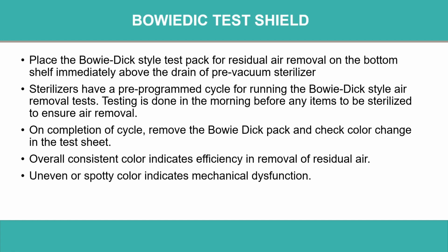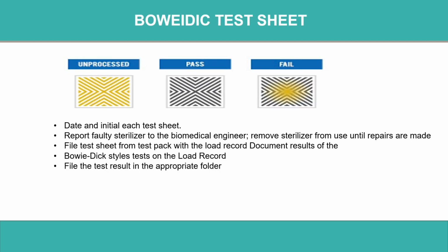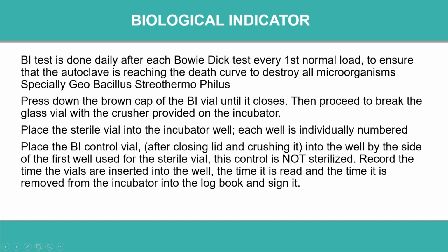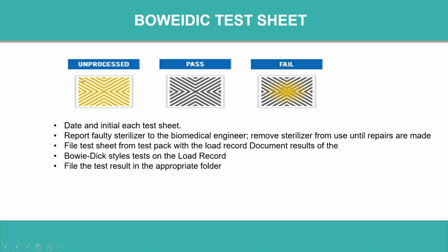These are the Bowie-Dick tests. What is a Bowie-Dick? Actually, this is a residual air removal test. There is a sheet; I'll show you in the next slide. See, this is the sheet. If you open the sheet and this pattern occurs, this yellowish color, this is unprocessed. After sterilization, if you open it and it looks like this one, it means it has passed. So we will go further; we can keep the load inside with the biological indicator. I'll show you the biological indicator after that.